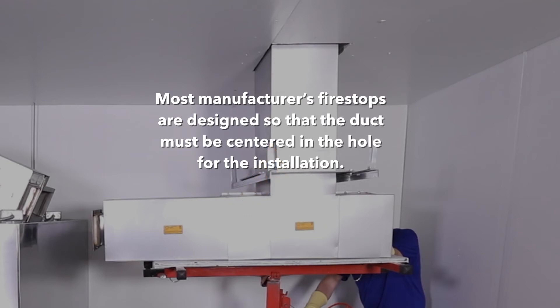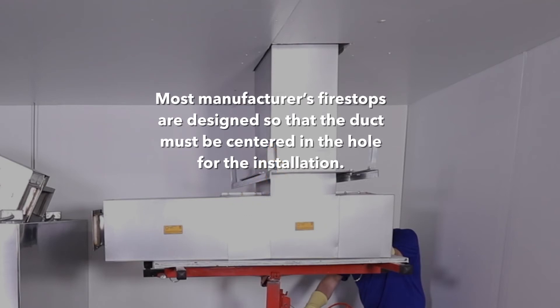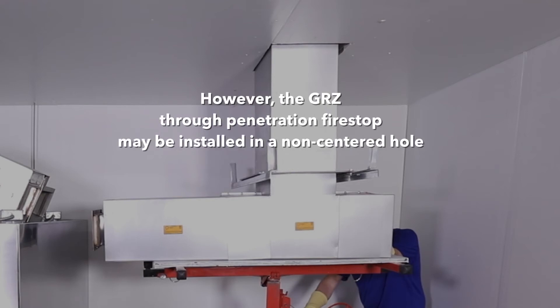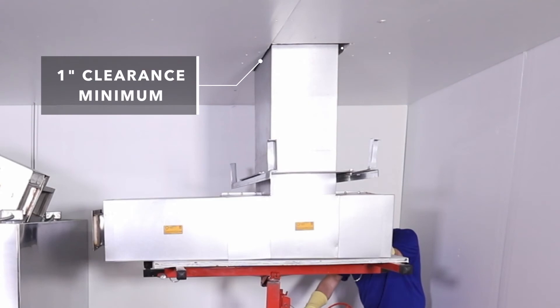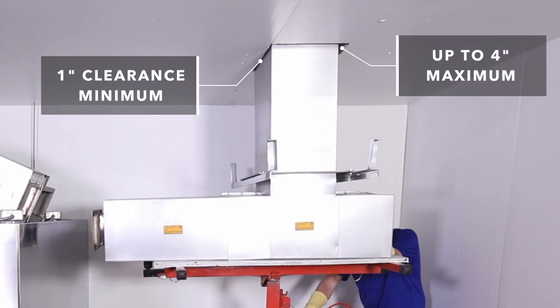The through-penetration fire stop deserves particular notice. Most manufacturers' fire stops are designed so that the duct must be centered in the hole for the installation. However, the GRZ through-penetration fire stop may be installed in a non-centered hole, with clearance as little as one inch on one side and as much as four inches on the other, or anywhere in between.